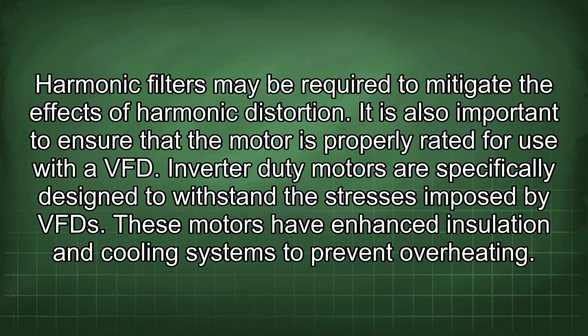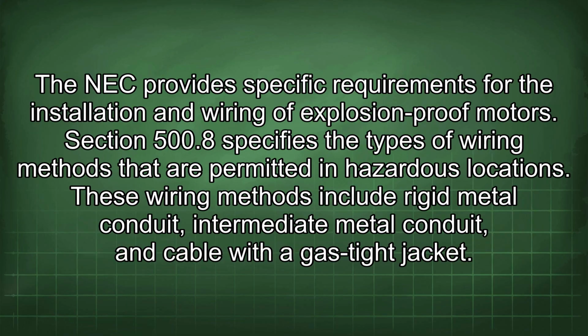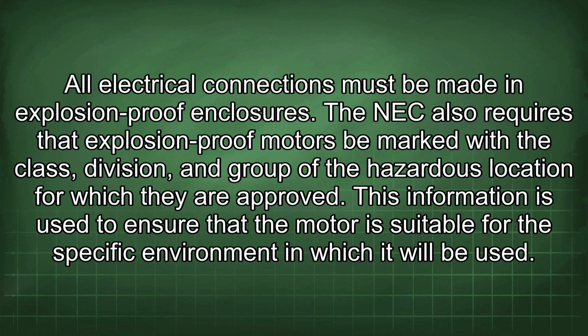Inverter duty motors are specifically designed to withstand the stresses imposed by VFD. These motors have enhanced insulation and cooling systems to prevent overheating. The NEC provides specific requirements for the installation and wiring of explosion-proof motors. Section 500.8 specifies the types of wiring methods that are permitted in hazardous locations. These wiring methods include rigid metal conduit, intermediate metal conduit, and cable with a gas-tight jacket. All electrical connections must be made in explosion-proof enclosures.